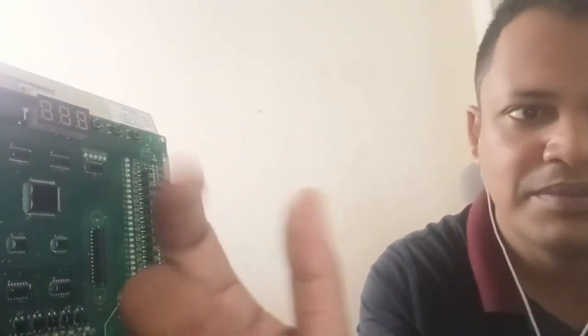Last of all, I want to show the main issue. If you don't realize it, you can check by keypad. What's the fault? Here the fault is shown, or not shown. You can connect the keypad here. You'll see it there, and you can change different settings. And I want to talk about another fault, of the gear motor. When there is an encoder fault, you can bypass it by setting F0000 to 0. Then the lift will run at inspection speed.